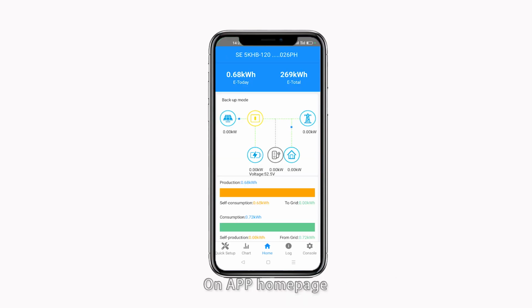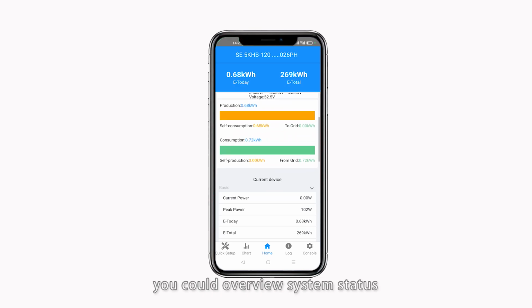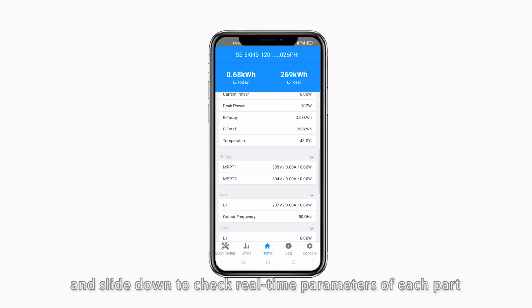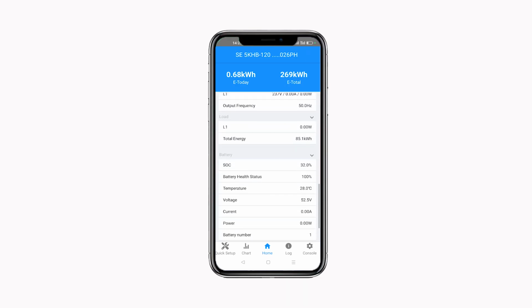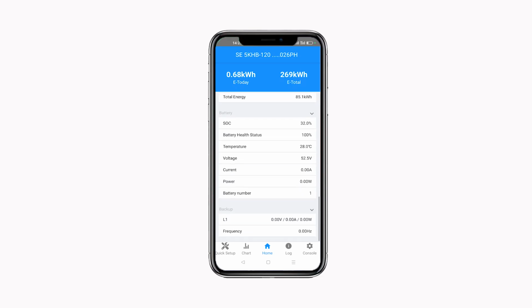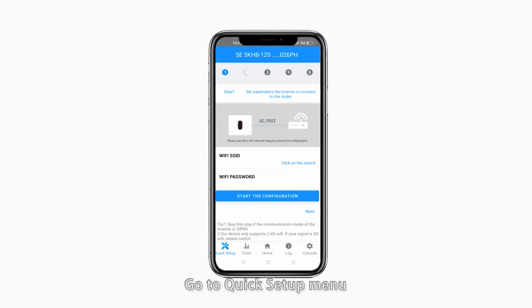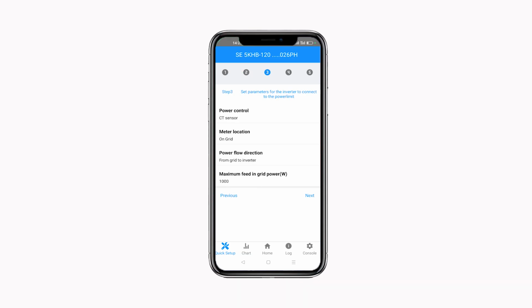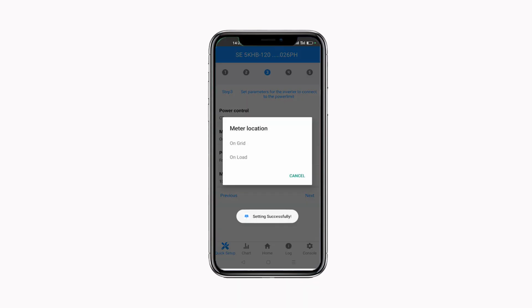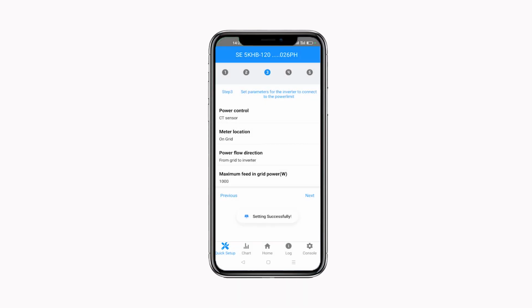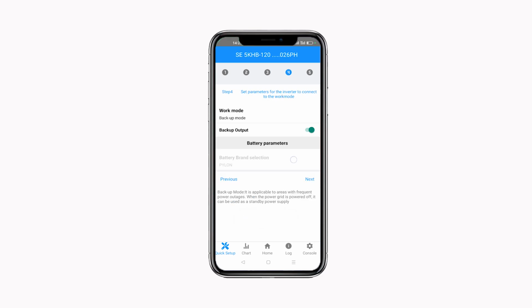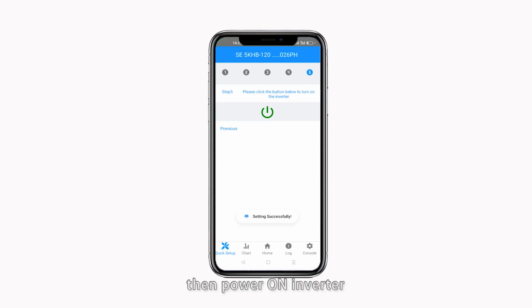On the app homepage, you can overview the system status and slide down to check real-time parameters of each part. Go to the Quick Setup menu, confirm the regulation setting, export power control setting, and working mode setting. Then turn on the inverter.